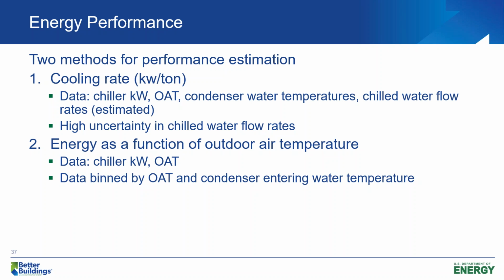So they used two methods of estimating performance. One was a cooling rate, trying to estimate the cooling rate in kilowatts per ton. They collected the chiller kW, outside air temperature, and condenser water temperatures, and then they were able to estimate the chilled water flow rate through a differential pressure measurement across the condenser, and then looking at the pressure curves provided by the manufacturers. But that gives you a pretty high uncertainty in that flow rate. So the second method was just looking at chiller energy as a function of outdoor air temperature. Further, they binned that data by the outside air temperature and the condenser entering water temperature, because each chiller has a different performance at different entering water temperatures.